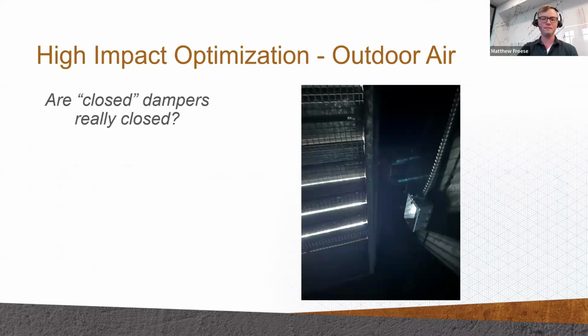This is another building we looked at, just had a controls upgrade, new damper actuators. Is your closed damper closed? And is your automation system giving you real information about what's happening mechanically? You can see the daylight through the damper, it's probably not really getting closed.